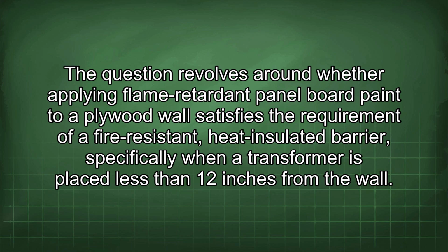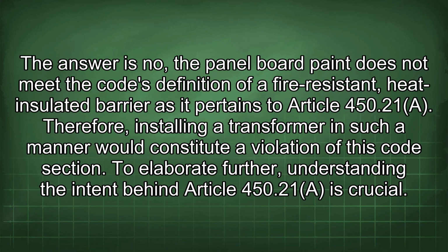The question revolves around whether applying flame-retardant panel board paint to a plywood wall satisfies the requirement of a fire-resistant heat-insulated barrier, specifically when a transformer is placed less than 12 inches from the wall. The answer is no. The panel board paint does not meet the code's definition of a fire-resistant heat-insulated barrier as it pertains to Article 450.21a. Therefore, installing a transformer in such a manner would constitute a violation of this code section.